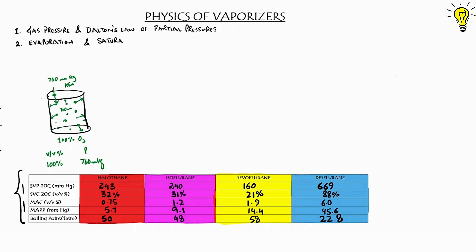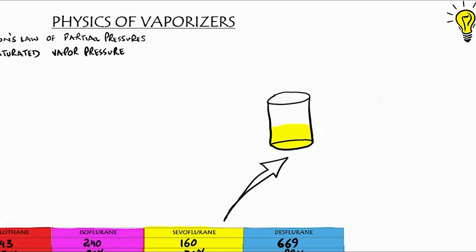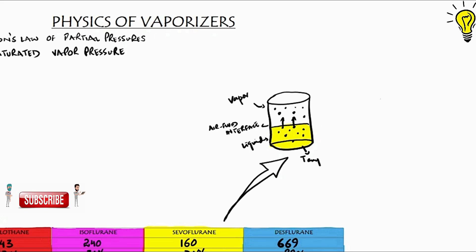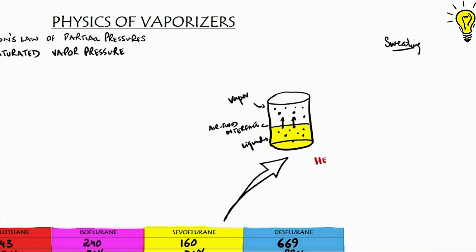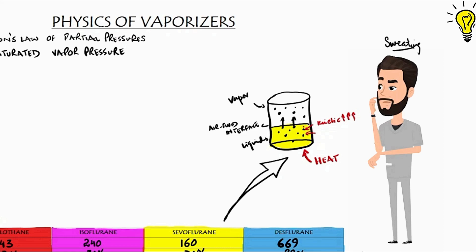The next principle to understand is evaporation and saturated vapor pressure. If we fill the chamber with sevoflurane liquid, the molecules of sevoflurane in liquid possess kinetic energy. At the air-fluid interface, this kinetic energy becomes strong enough for the molecules to overcome the liquid forces and escape as vapors into the air. But this process requires energy which is taken from the remaining fluid, so vapor formation results in a drop of temperature of the remaining fluid — just like when sweat vaporizes off our skin surface, the process of vaporization pulls away heat and energy from the skin. This is why our skin gets colder after the sweat vaporizes.